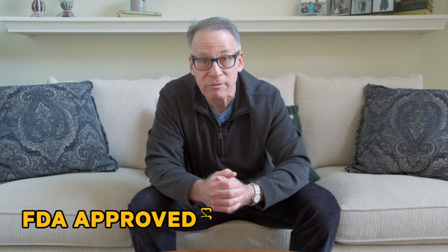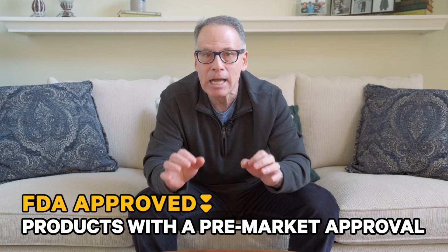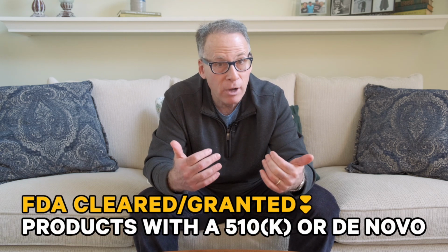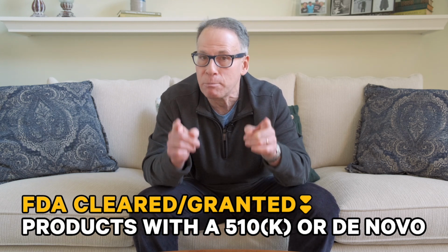Only products or platforms that secure a pre-market approval, or PMA, are legally allowed to be marketed as FDA approved. Platforms that go through the less rigorous process of a 510(k) or de novo are considered FDA cleared or granted respectively, not approved. FDA exempt or registered only products may not be marketed as FDA anything. There's a link below to an excellent blog on this topic. Most products go through the 510(k) process, so most of the time we're referring to an FDA clearance, not an approval.